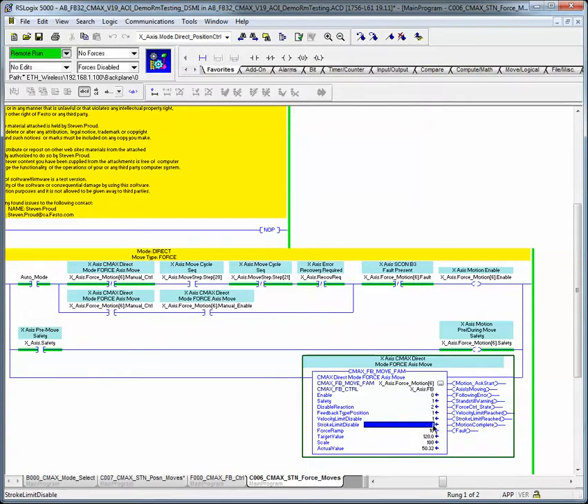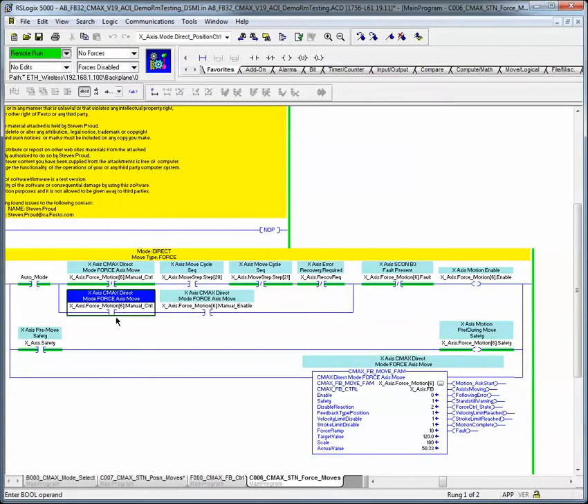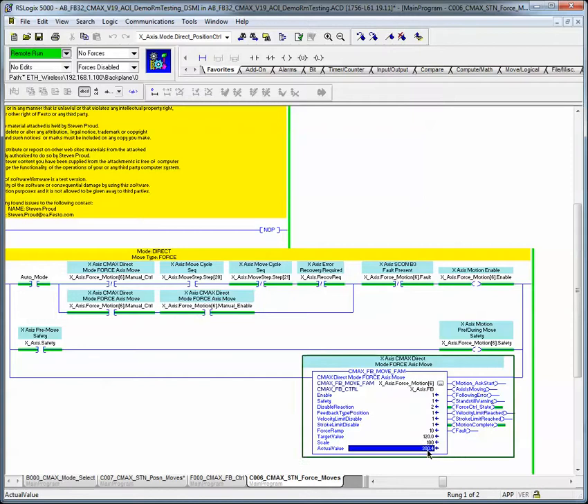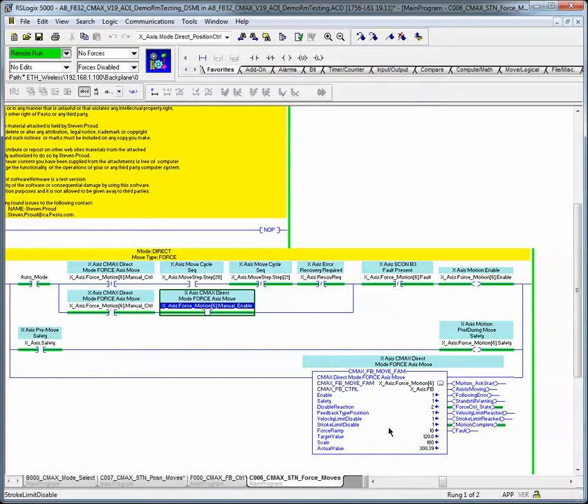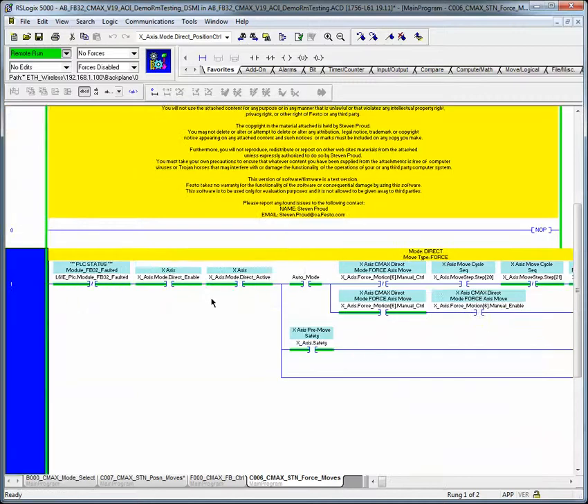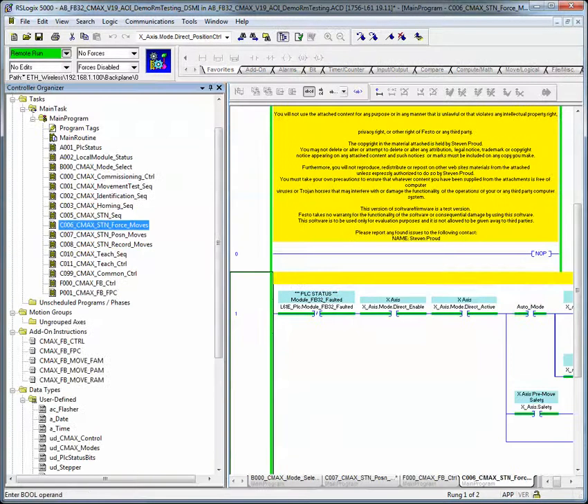I'm disabling that so I'm at position 50 right now and I'm just going to let it go the full stroke. I'm going to turn the axis on — the axis is moving, applying a small force. Motion complete, meaning you've reached the value. And if I was monitoring for force, it would show a different value right here. I'm going to turn this off. Because the disable action is two, it's going to go into position mode. So there's a quick overview of all the function blocks.